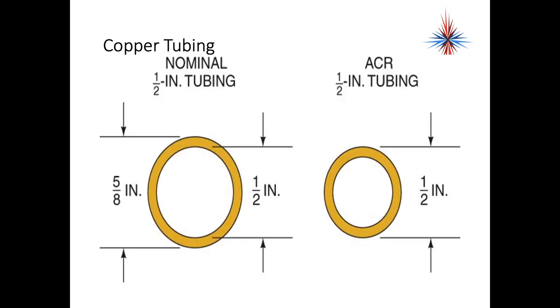When we look at copper tubing, a half inch nominal tubing is actually five-eighths inch ACR. It's the same tubing, it's just measured in two different ways. Half inch ACR tubing actually fits inside half inch nominal tubing.